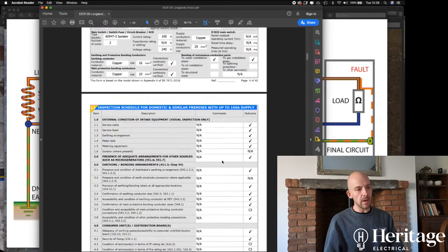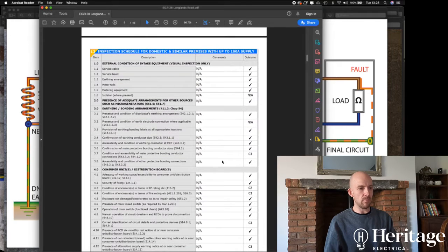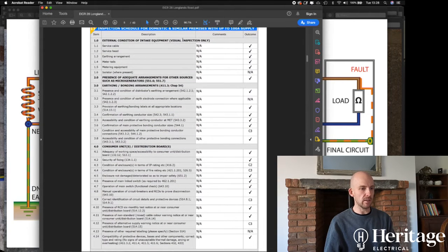Next up is our list of inspections that we carry out. Now, some of these are purely a visual inspection, like all the intake equipment, so the service cable, the cable that comes into your property that actually supplies the property, and the service head that's got the fuse in, the earthing arrangement, etc. We just do a visual inspection. All of that stuff, the supply and intake equipment, is the responsibility of the network operator to maintain and come and fix any problems with. So if there are any problems from that part of the installation, we advise you to get in touch with the network operator, and they will come and sort out those problems free of charge.